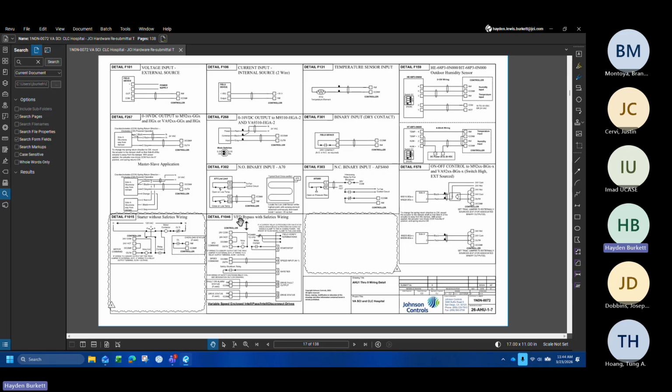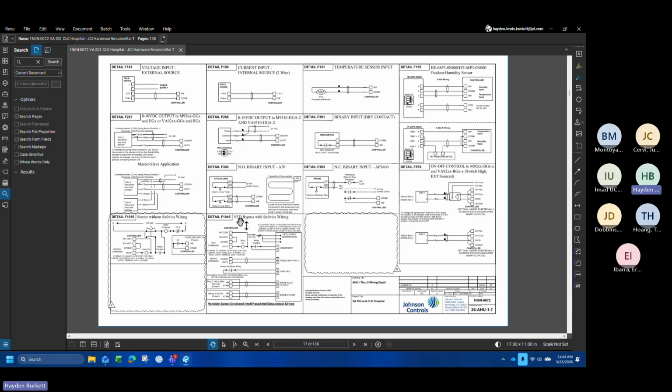Yeah, so that's an excellent question. Worth noting, at least with our site, this project, both of these sensors are mounted approximately 12 to 14 feet up in an area that's in the shade essentially 80% of the day. So while it might pick up some of that radiant heat that you're referring to off of the laminate roofing, I think it's going to be pretty minimal.